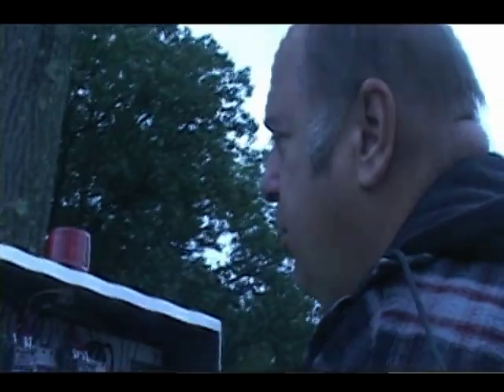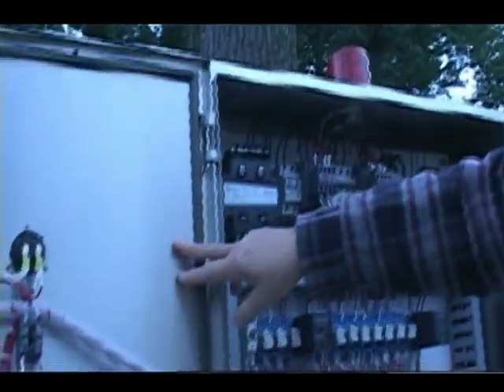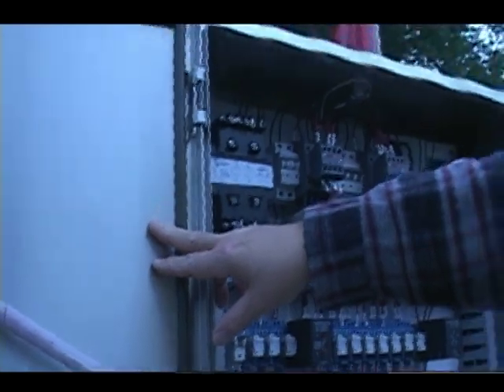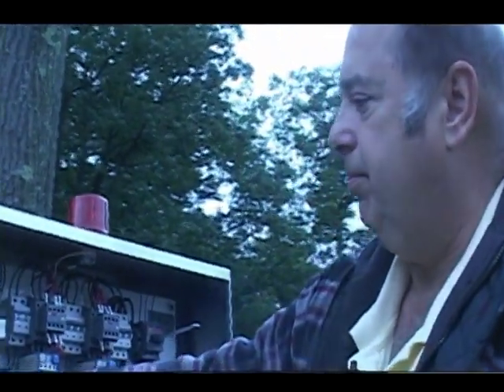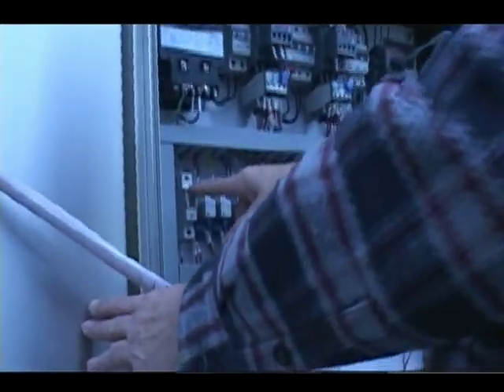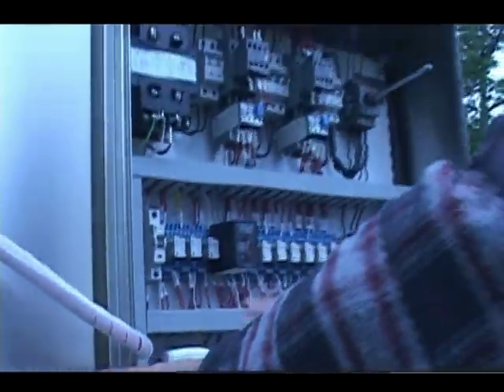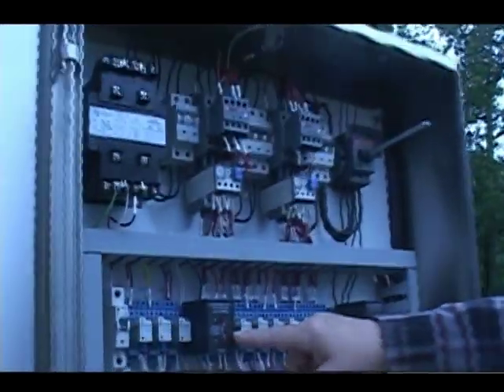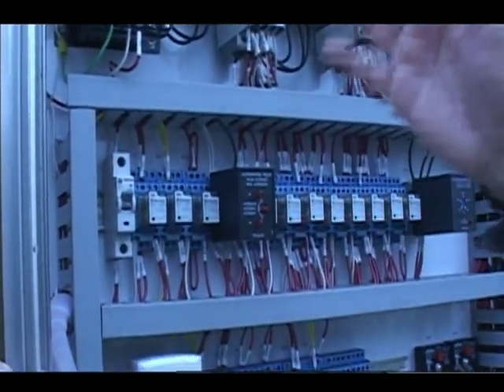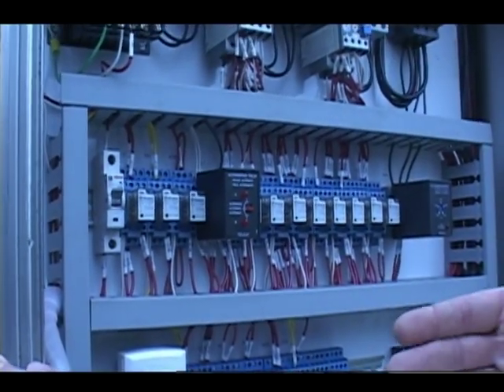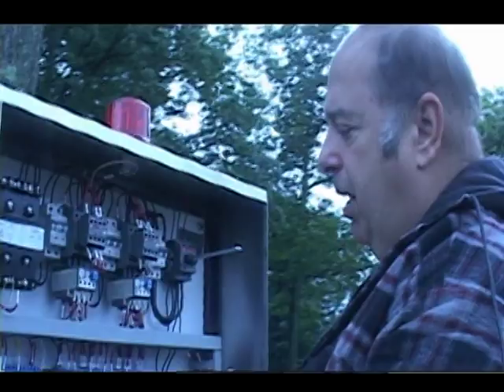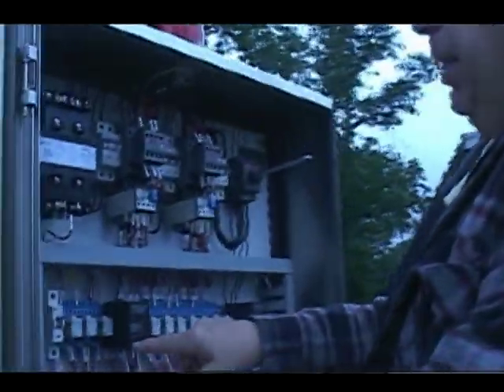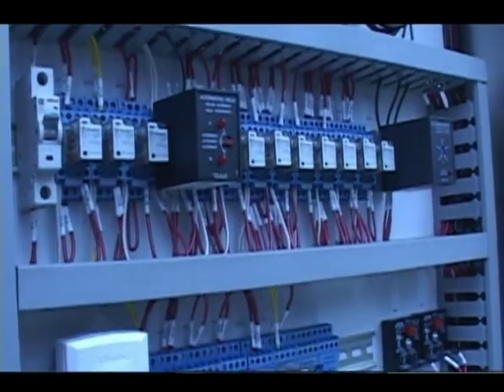Okay. Now, there's a control transformer here, which takes it from 460 to 120 for our control power, and its own circuit breaker to protect it. For this 110 volt side, it has its own circuit breaker, which if it's tripped, the whole unit shuts down. Okay. We have an alternator, so that each pump cycle, it'll switch between pump 1 to pump 2. If for some reason you want one of the pumps to be the lead pump, you would switch it to either A or B for it to stay, so that pump 1 is the lead pump all the time, or pump 2, depending on what you'd want.